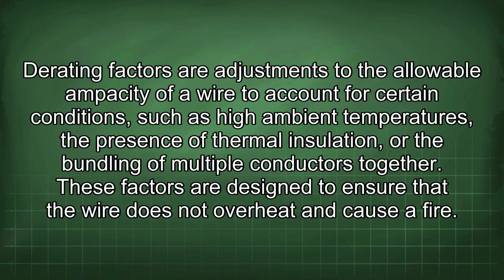Derating factors are adjustments to the allowable ampacity of a wire to account for certain conditions, such as high ambient temperatures, the presence of thermal insulation, or the bundling of multiple conductors together. These factors are designed to ensure that the wire does not overheat and cause a fire.